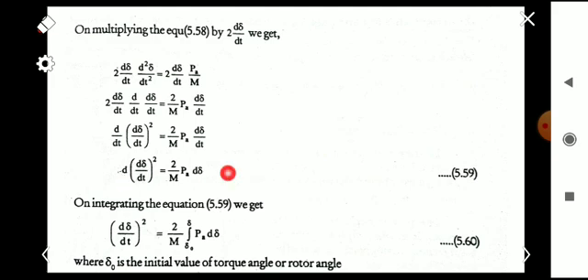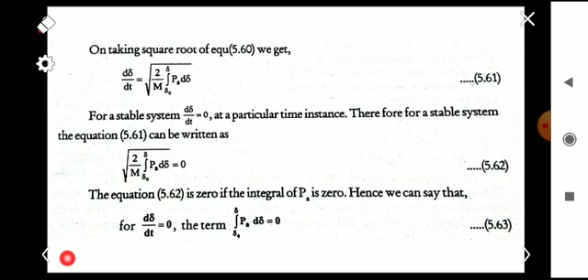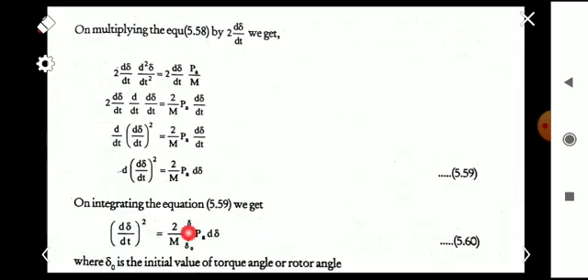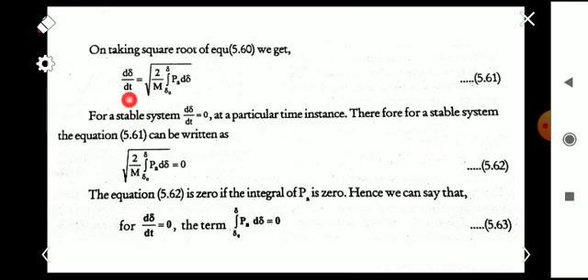Integrating both sides, the left-hand side becomes (d delta by dt) squared. The right-hand side, since 2 by M is a constant, becomes (2 by M) times the integral from delta_0 to delta of P_a d delta, where delta_0 is the initial value of the torque angle. Taking the square root of both sides: d delta by dt equals the square root of (2 by M) times the integral from delta_0 to delta of P_a d delta.